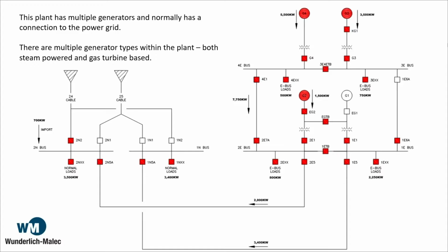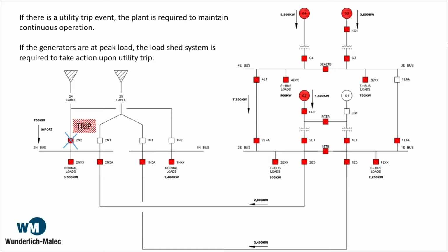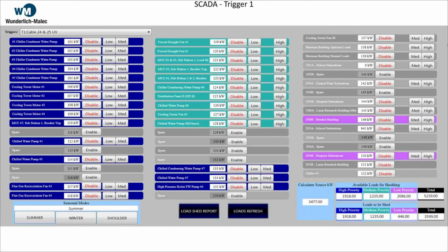So in this example, we've got a plant here with multiple generators, and it's designed to normally have a connection to the power grid. Now let's say we have a utility breaker trip. If we're already running at maximum output on our generators, we're gonna have to do something. We're gonna have to remove some electrical load. Could be a chiller or a water pump. So we've got to take action very quickly. Let's move to the next slide. And I'm going to let Chris Rowland speak about this. So in our plant, I'd like to describe the fact that we've got multiple generators that use different prime movers. We've got gas turbines, we've got steam turbines, and we've got to balance the electrical load while also being able to meet the day-to-day operational constraints.